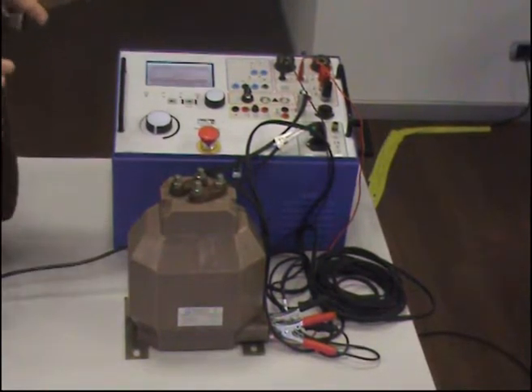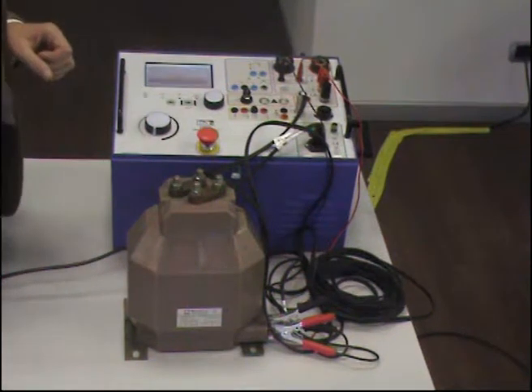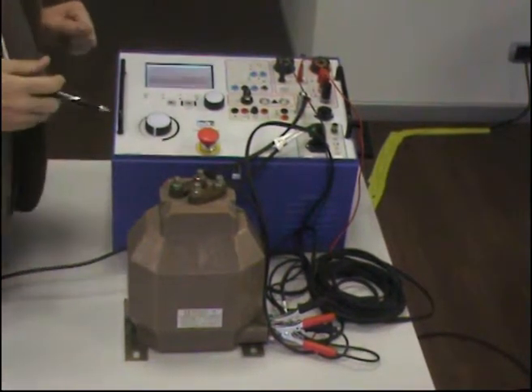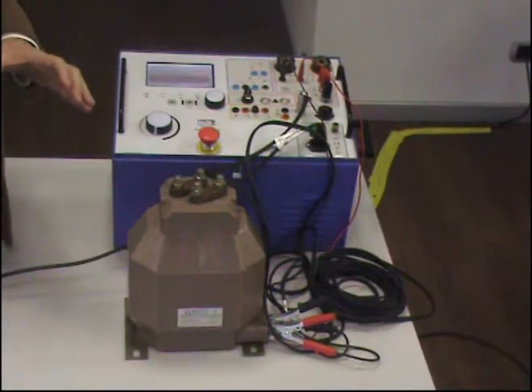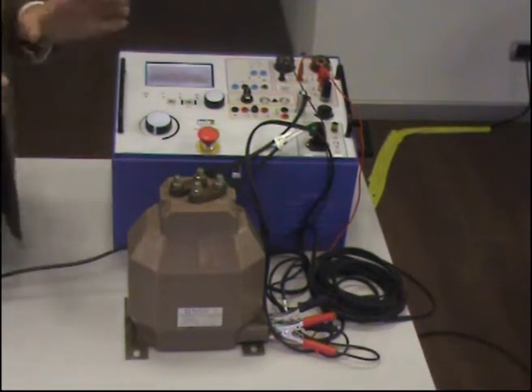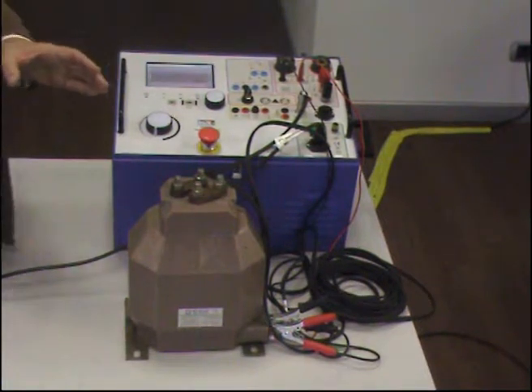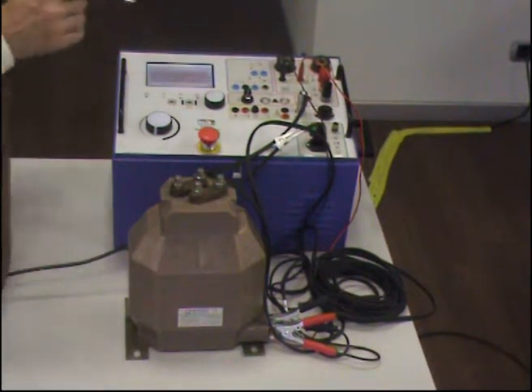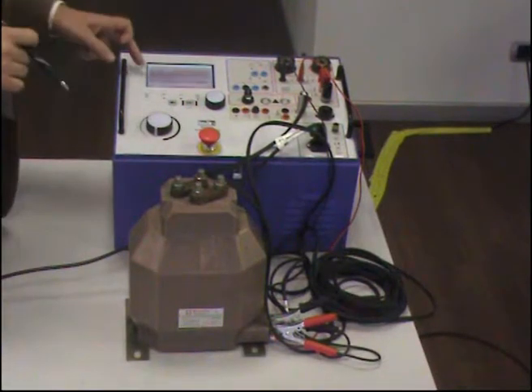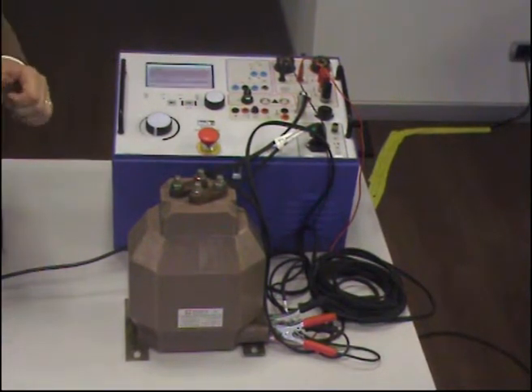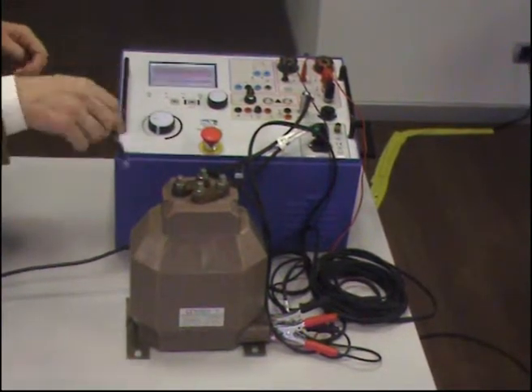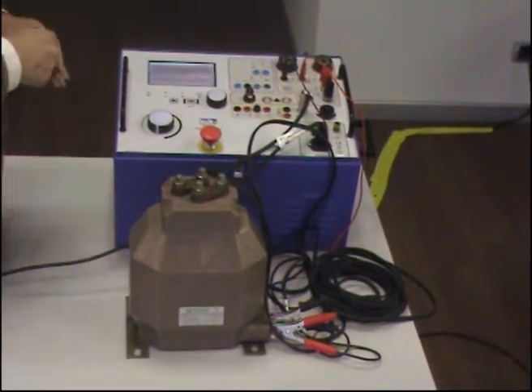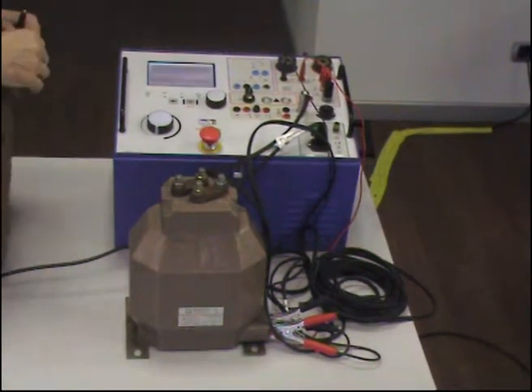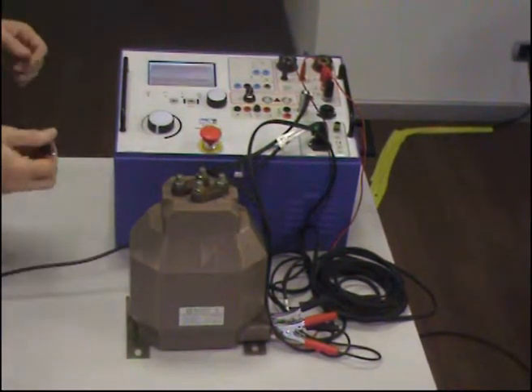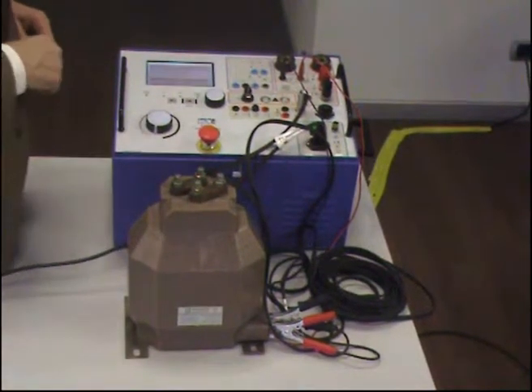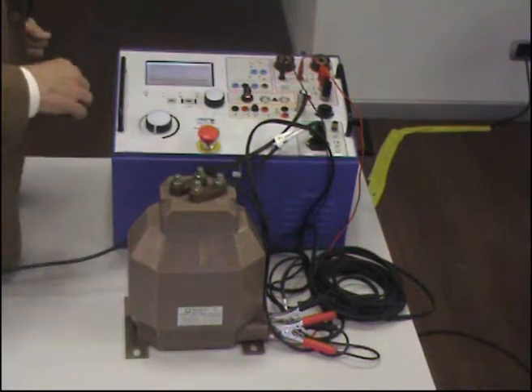Generally speaking, you have to take real care when you are performing this test. Why? Because we are generating a DC current, and by definition the DC current is saturating your transformer. It is saturated. So, after this test, it is absolutely advisable to perform another test with AC so that you remove these remnants that are surely there. The other thing is that according to the dimension of your current transformer, there could be a problem that you can be facing.